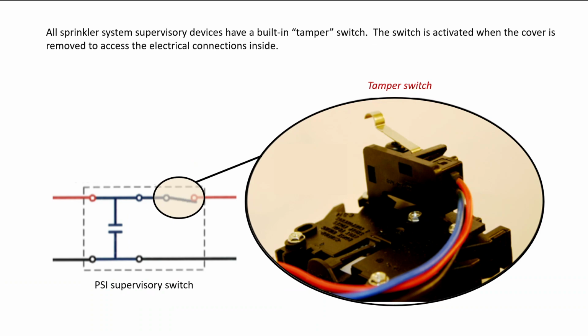All sprinkler system supervisory devices will have a built-in tamper switch. The switch is activated as soon as the cover is removed, and the cover needs to be removed in order to access the electrical connections inside. It's a spring-loaded micro switch which is connected in with the wiring. When a tamper switch is triggered, it initiates a supervisory condition at the fire alarm panel.